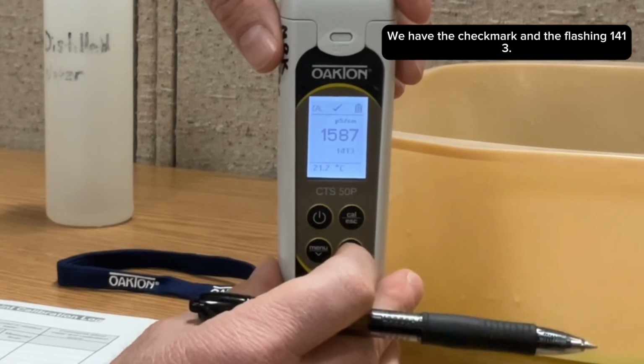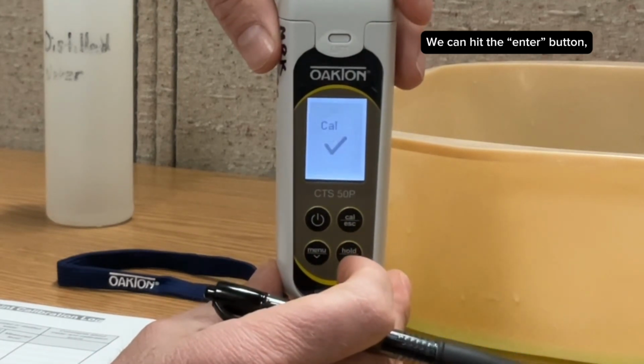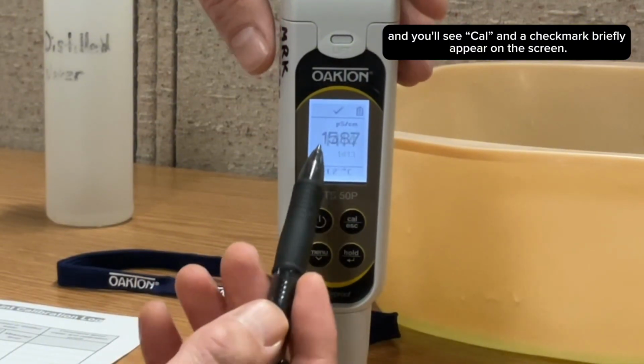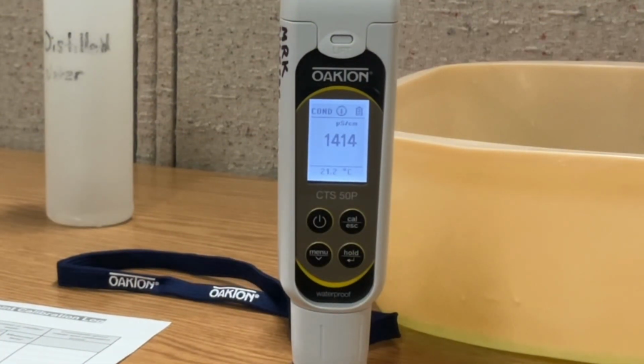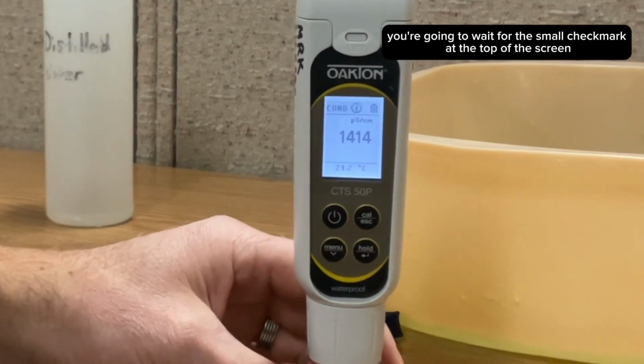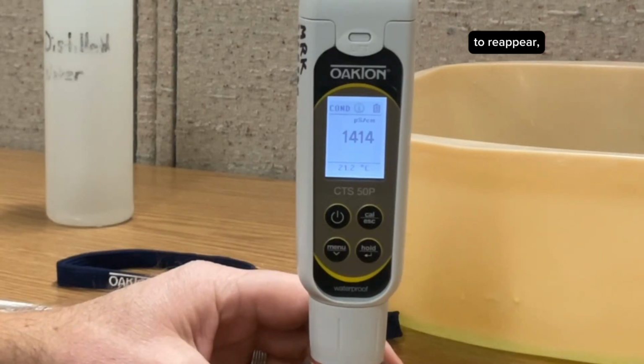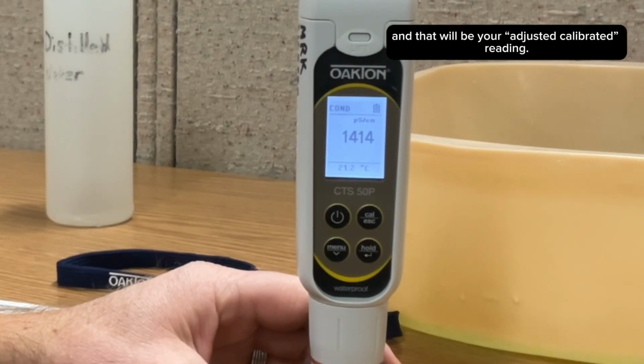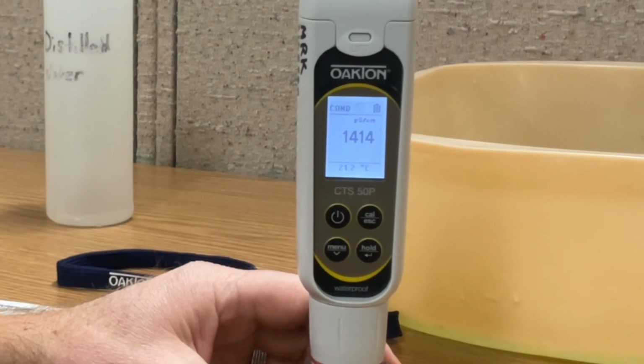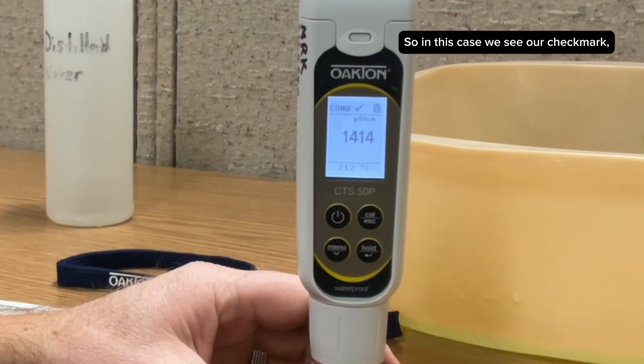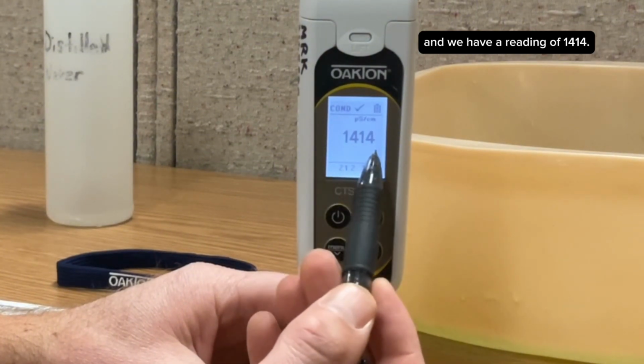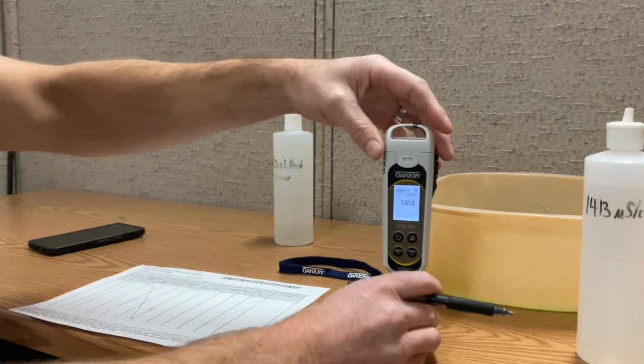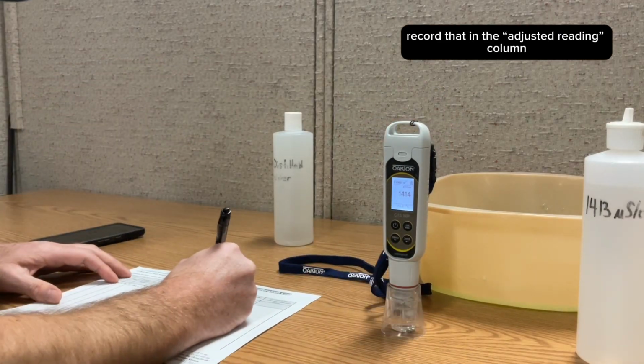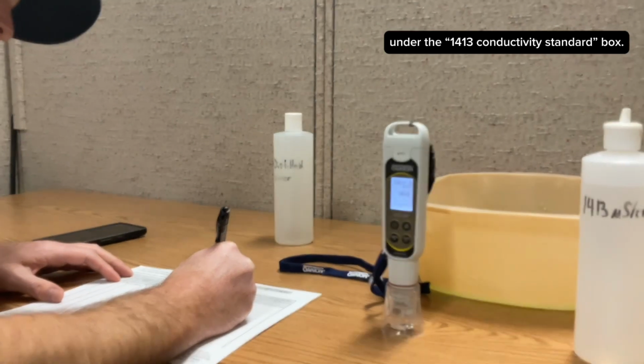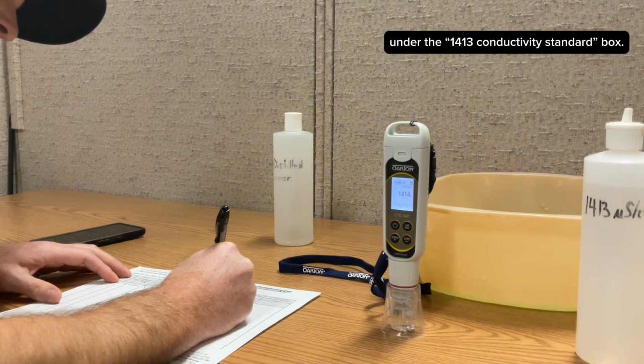With the check mark and the flashing 1413, we can hit the enter button and you'll see a cal and a check mark briefly appear on the screen. From there, you're going to wait for the small check mark at the top of the screen to reappear, and that will be your adjusted calibrated reading. So in this case, we see our check mark. We have a reading of 1414. So we're going to go ahead and record that in the adjusted reading column under the 1413 conductivity standard box.